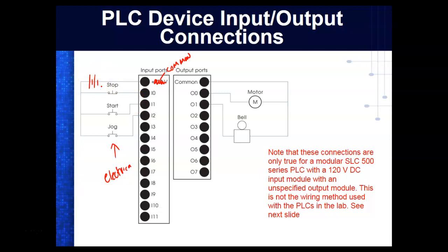So both these PLCs are running sinking inputs, which means the minus has to point toward the common on the PLC, and then the plus, which means the devices themselves, is what we call sourcing. And then on the 1100s, the MicroLogix 1100s, Rich, it's using sourcing output, so we'll need to point our DC supply with a plus toward the output. Are we okay?